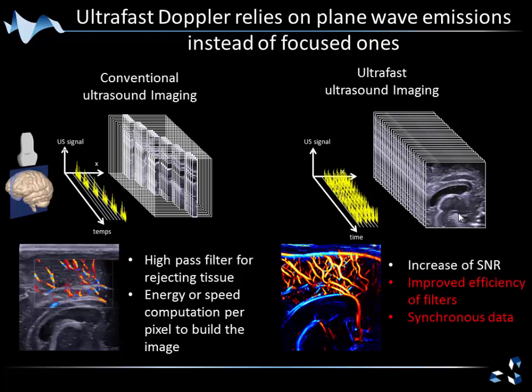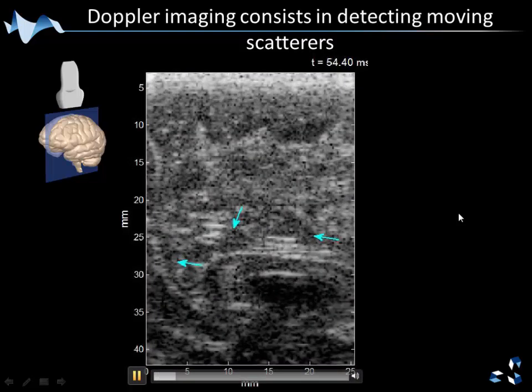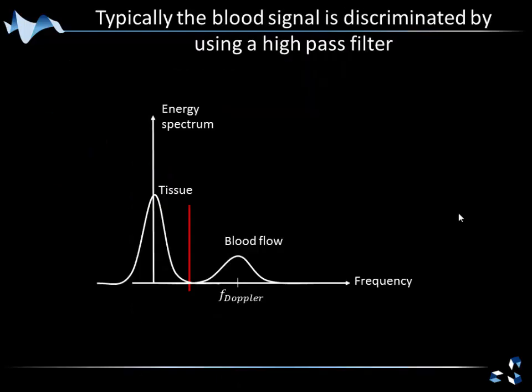It's the same vascular image in a human neonate brain, but it also implies improved efficiency of filters, and you have synchronous data. Doppler imaging consists in detecting moving scatterers. This is an ultra-fast data movie of a human brain in a neonate — you can see the speckle moving in some locations. We want to discriminate between tissue and blood flow. The classical way to do this is a high-pass filter: the tissue is centered on zero frequency and the blood flow on the Doppler frequency, and the high-pass filter cuts in between.